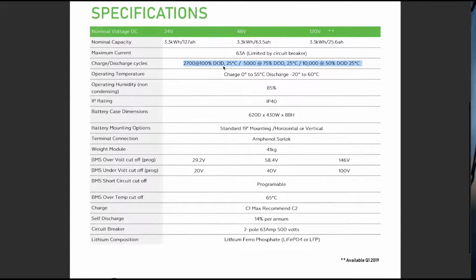So let's say we're going to 100% depth of discharge, and we're getting 2,700 cycles. So we'll try that. That means if I wanted to build a comparable system where I'm using 100% of the lithium battery's capacity, and I need to build something that's got 72 kilowatt hours usable, I take 72 and divide it by 3.3. So I need 21.8. Let's call it 22 battery modules. Whoa, that's a lot of battery modules, but yep, it can be done.